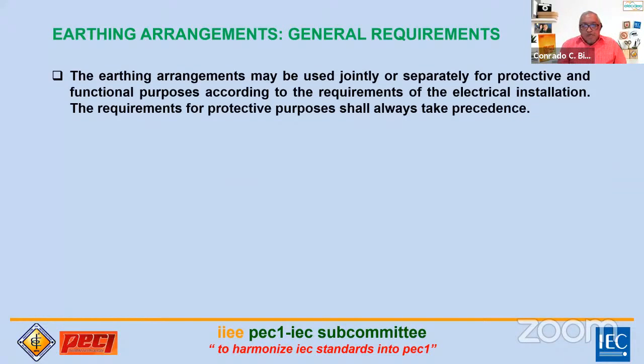You cannot just mix these together or separate them arbitrarily. There are discussions where they say the grounding should be separate because they don't want it to affect the equipment, the electronic or whatever equipment it is. So take note, even in PEC and IEC standards, the point is that protective purposes are more important, because when a person gets electrocuted, that life is more important than the equipment. We have to check that mindset.